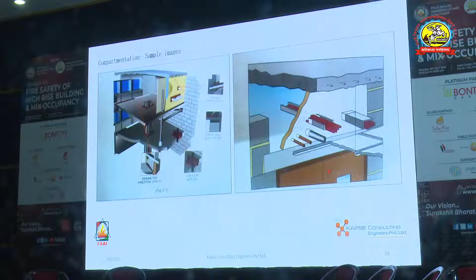So you have appropriate passive measures to seal that hole. You can put a collar, which is a strip that we call a collar, around the rainwater pipe. If there is heat below, the collar melts and it closes the hole. But if you just put cement around the pipe, it's of no use.